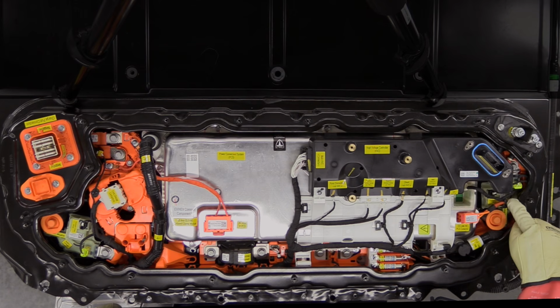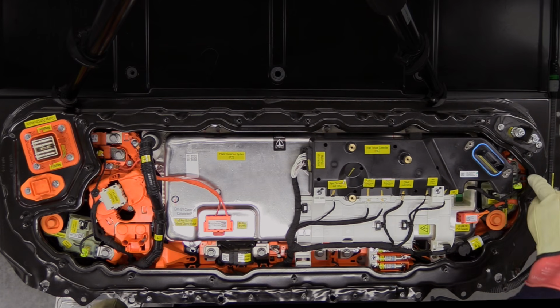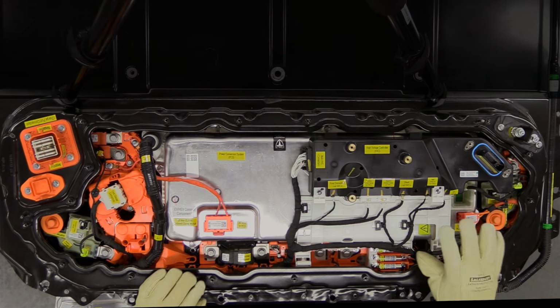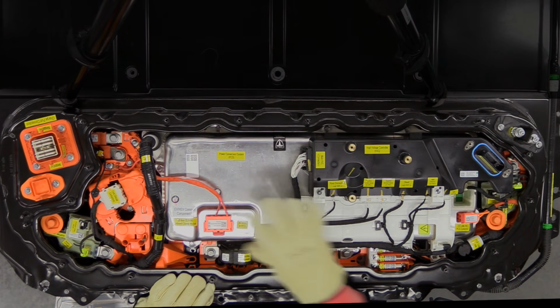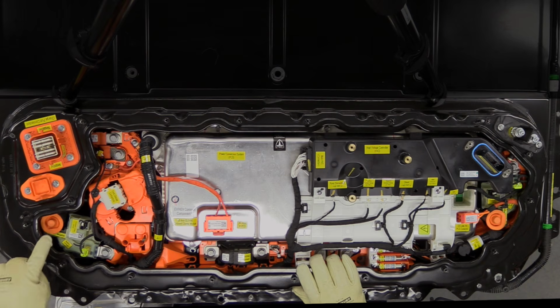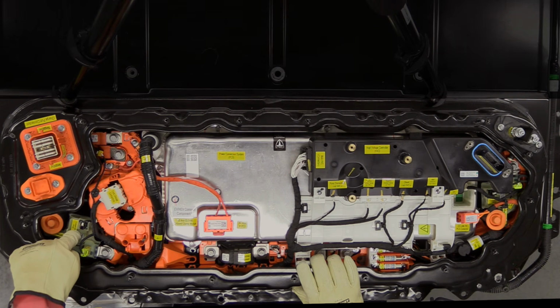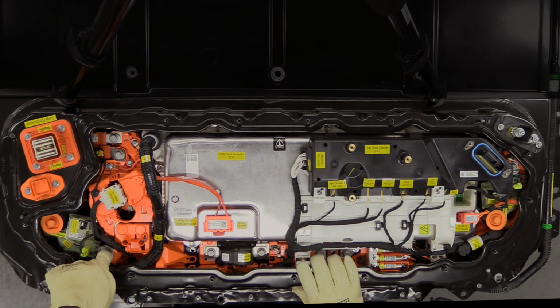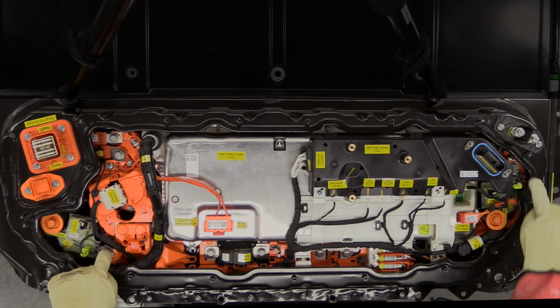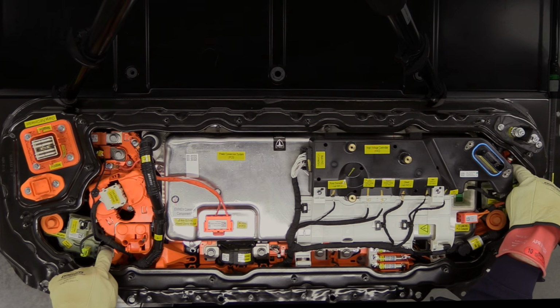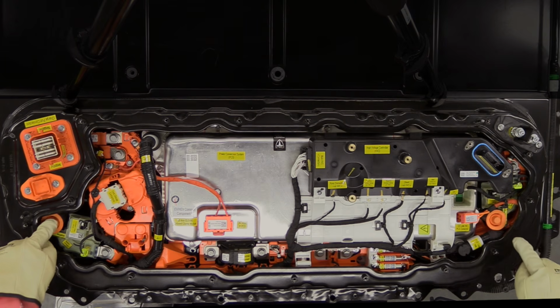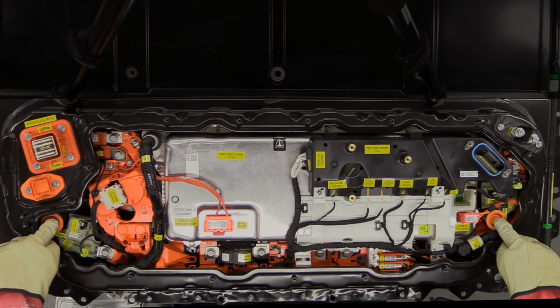When this contactor turns on, it connects this post to this post, which then applies positive high voltage to the rest of everything underneath the cover here. Over here, our negative terminal is connected to the contactor, which is normally open and off. So there is no negative right here. And that means that if I were to touch a voltmeter between this point and this point over here, it would be 0 volts. If I put it between these 2 points, it would be upwards of 400 volts.